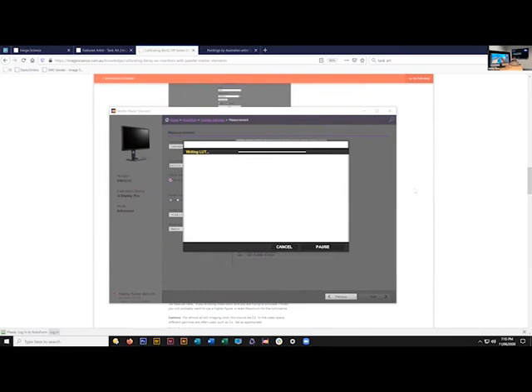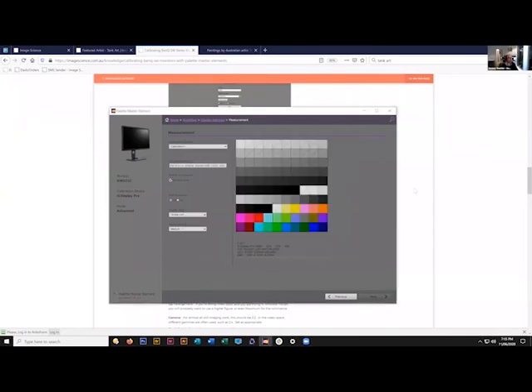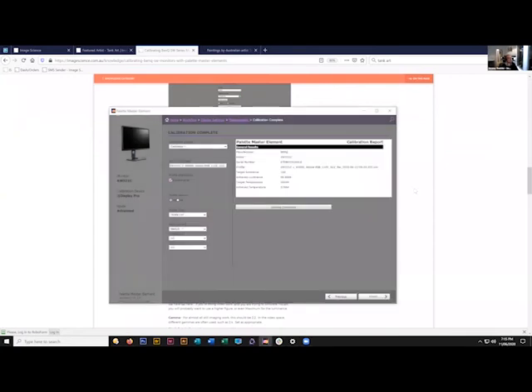Okay. We have a question from Caleb. Is validation failure a sign of faulty monitor, faulty calibrator, or something else? It's usually something else. Well, it's very rare that it is faulty. It can be both of those things for sure, but it's very often not those things. It's almost always some sort of software idiosyncrasy. It's a very difficult one to actually pin down why it's failing, and it depends where the failure is.